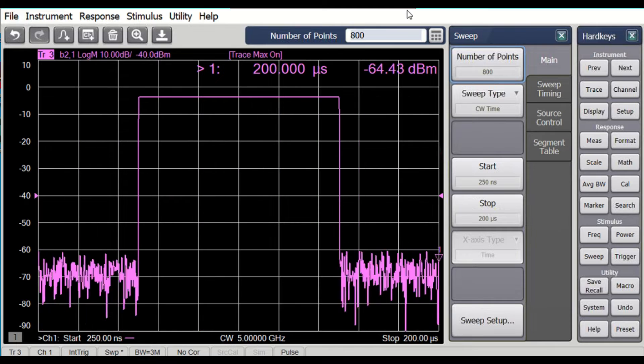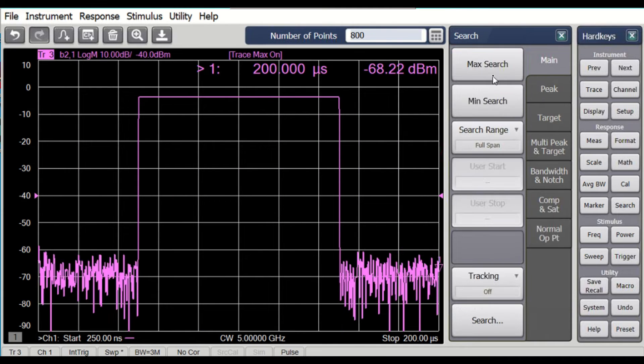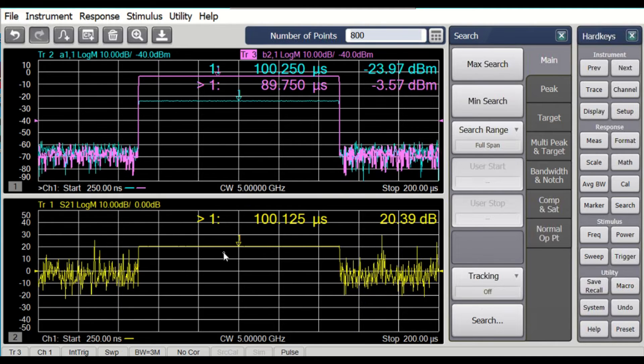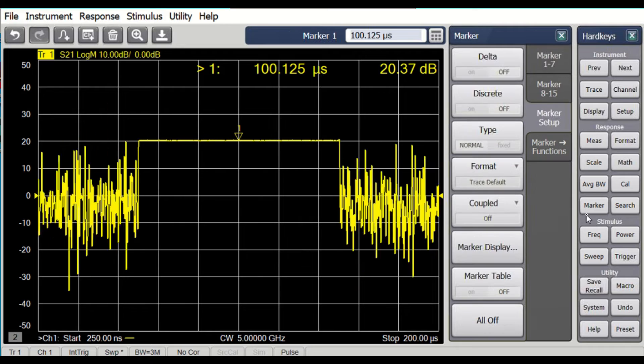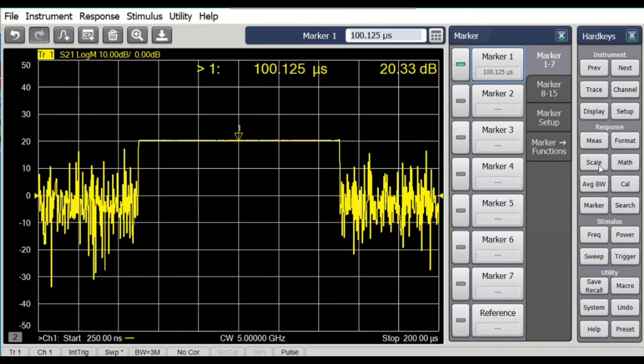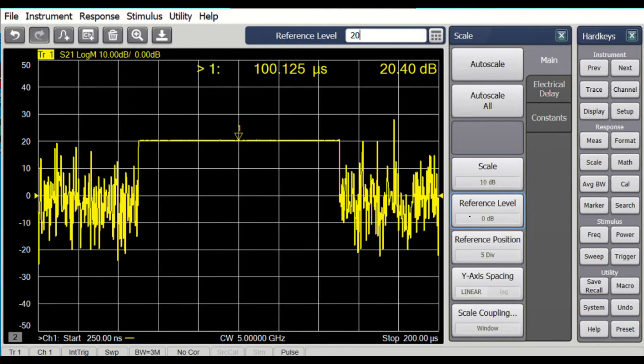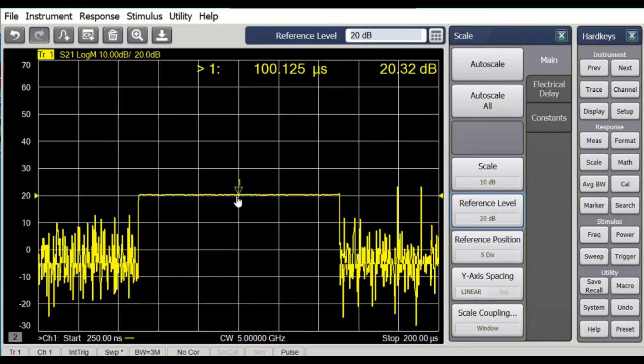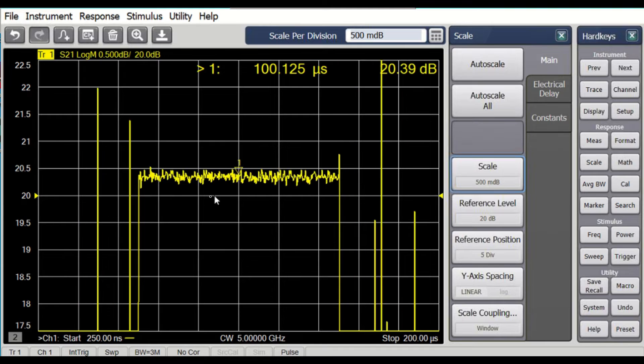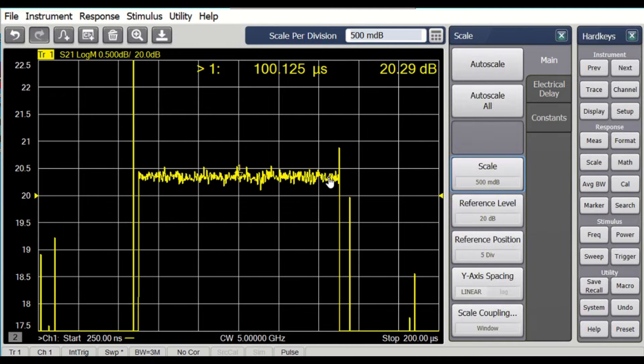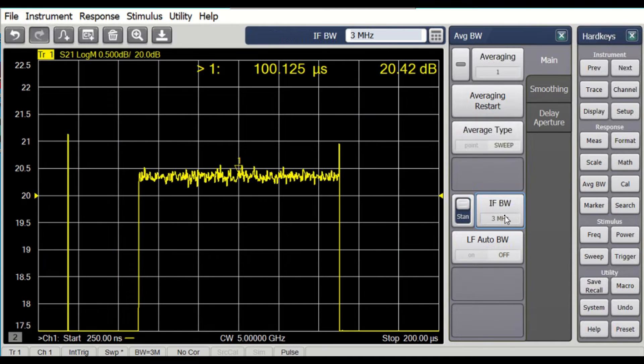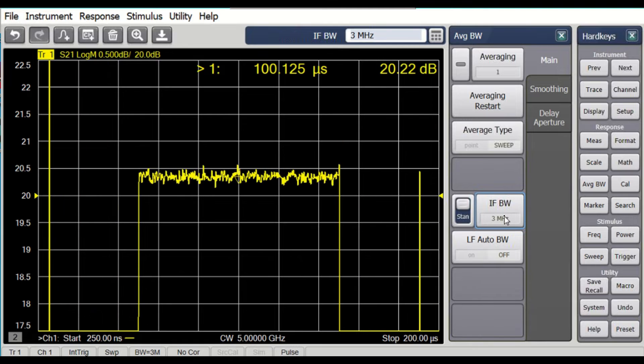Going back to 800 points, we'll put the marker back at the maximum of the pulse. Besides looking at the pulse power, we can look at the pulse phase. Let's look at this S21 — I'll set the marker reference to 20 dB. Now we can see a lot of noise on this measurement because I've made the IF bandwidth large, which lets in a lot of noise. If I try changing the IF bandwidth, I'll get a somewhat strange result — let's make it 100 kHz.